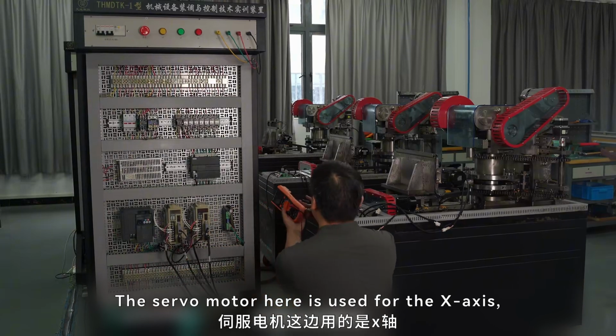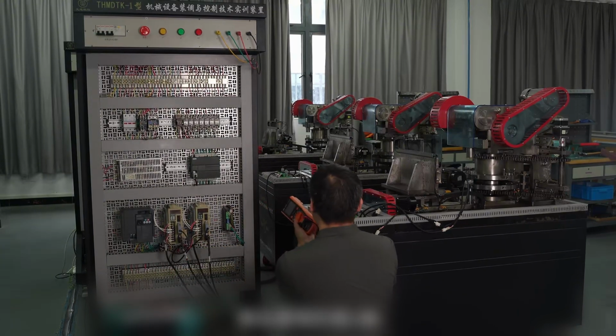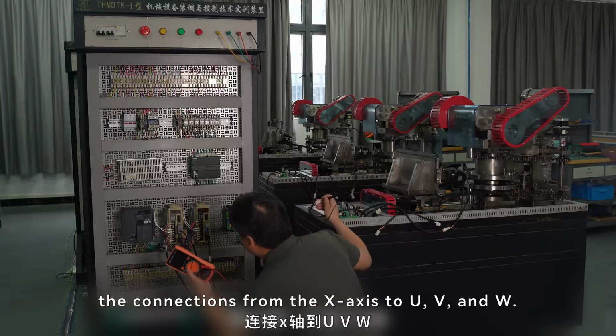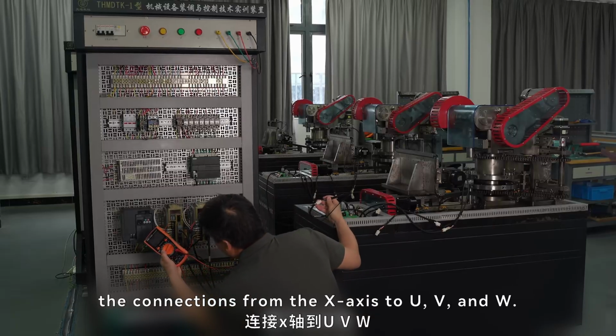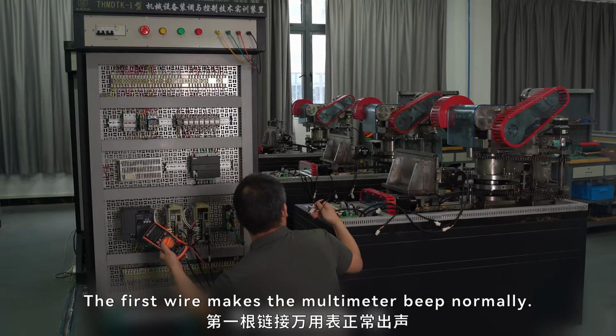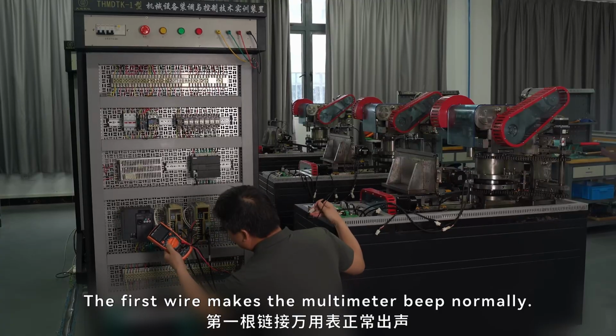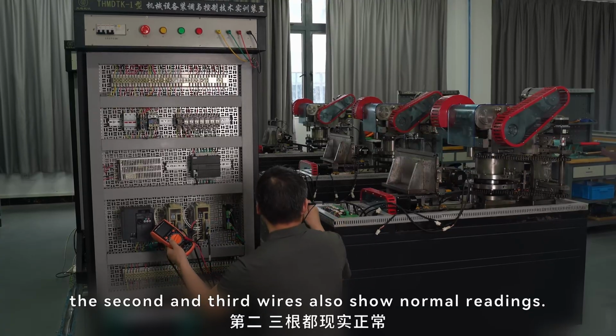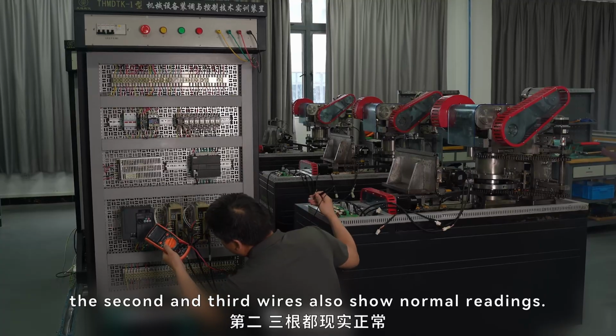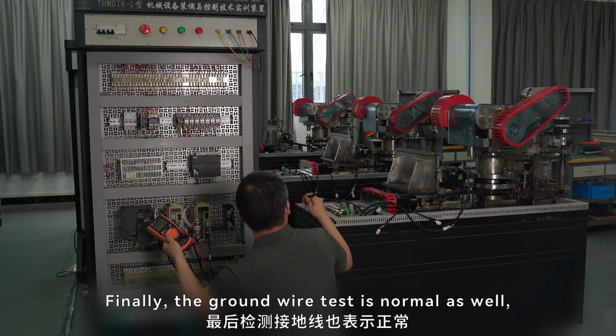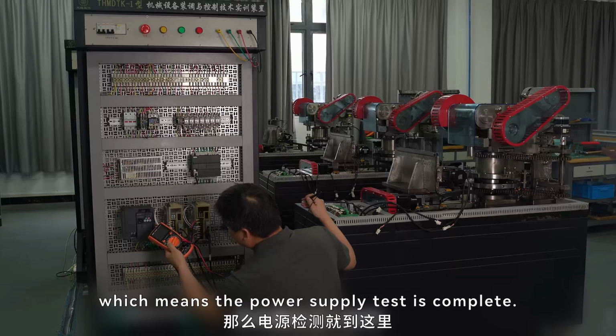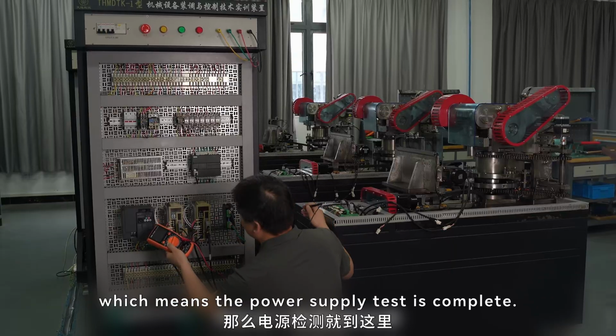The servo motor here is used for the x-axis, and we use a multimeter to test the connections from the x-axis to U, V, and W. The first wire makes the multimeter beep normally. Then, the second and third wires also show normal readings. Finally, the ground wire test is normal as well, which means the power supply test is complete.